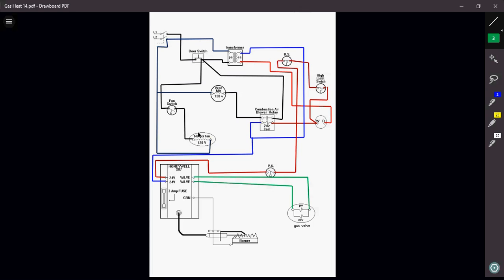Once that thermostat satisfies and the room reaches its temperature, the thermostat opens, and when it opens, it de-energizes the coil for my vent motor. That de-energizes, so that contact is going to open, shutting off the vent motor. And when that vent motor stops spinning, that pressure switch is no longer going to sense that pressure difference, and it's going to open. And when it does, my 24-volt signal to my ignition module is now gone. My gas valve is going to close. The burner is going to shut off.